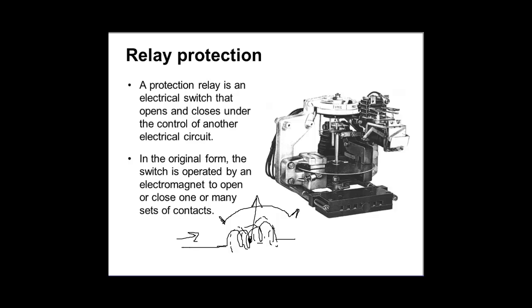This is what I said when I was talking to you in terms of metering, measuring. That's one application. Well, I can use the same concept, but this time for protection, not for metering. Like what? Okay, see this? Again, this relay has got exactly the same mechanism. It has got the permanent magnet. See that disc? Replace that disc with that pointer, with that needle.